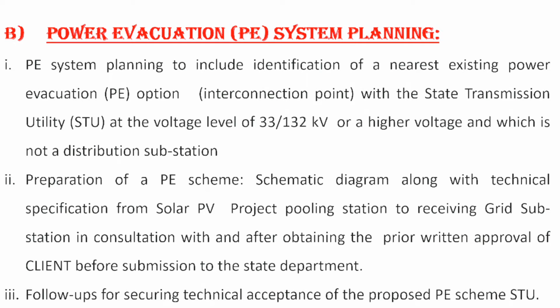Suppose it is 33 kV, and you are getting 660 volts from the solar plant of say 1 megawatt. Now you have to convert it, step it up to 33 kV to get the connectivity, to evacuate your solar energy to the grid. So then you have to provide a transformer of 660 volt to 33 kV, a step up transformer.